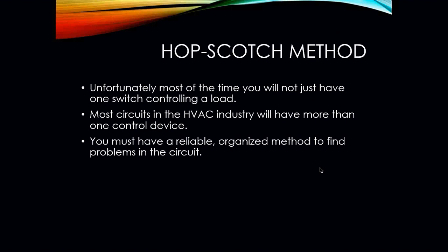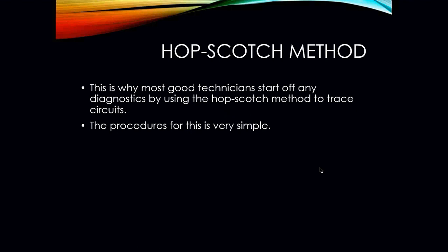However, unfortunately, most of the time you will not just have one switch controlling a load. You may have multiple switches controlling a load. But most circuits in this HVAC industry will have more than one control device. So you must have a reliable, organized method to find problems in that circuit. So we use what is called the Hopscotch method. Okay, this is a good way to start off any sort of diagnostic on an HVAC system, by using the Hopscotch method. And the procedure is relatively simple.